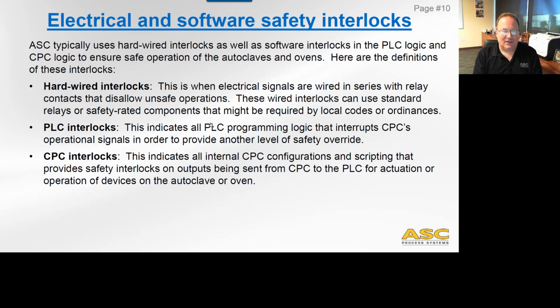Electrical and software safety interlocks. So for the rest of the training class, we'll talk about three sets of interlocks that we're going to go through: hardwired interlocks, PLC interlocks, and CPC interlocks. So ASC typically uses these interlocks to provide safe operation of our autoclaves and ovens. Hardwired interlocks, what is that? This is when electrical signals are wired in series with relay contacts that disallow unsafe operations. These wired interlocks can use standard relays or safety rated components that might be required by local codes or ordinances. So in most of the European applications, they're going to require safety rated components, whereas in the US we are still allowing in general safety to use standard relays for that.